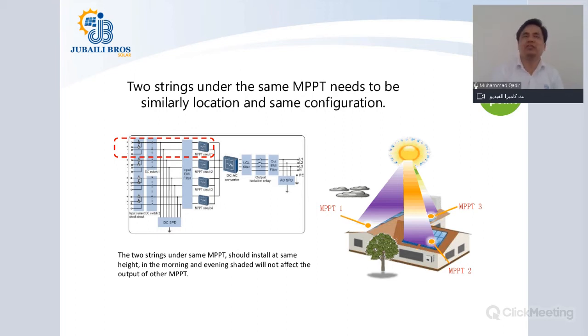Similarly, the length of the strings in one MPPT should be the same. So you can have different string lengths in different MPPTs, and you can have different tilt angles in different MPPTs, but you must make sure that you have the same string length and same orientation for one MPPT. Otherwise, a different configuration or different orientation on the same MPPT will lead to power production losses.